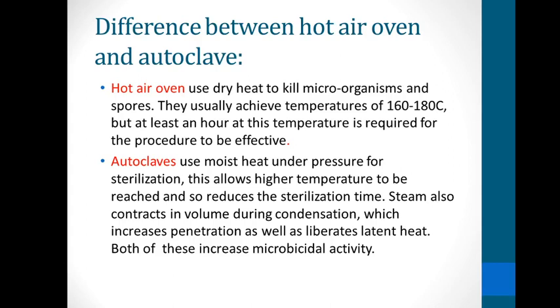Hello, today we're going to talk about the difference between hot air oven and the autoclave. A hot air oven uses dry heat to kill microorganisms and spores. They usually achieve temperatures of 160 to 180 degrees Celsius.